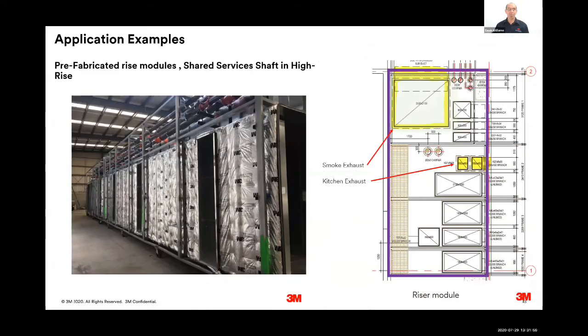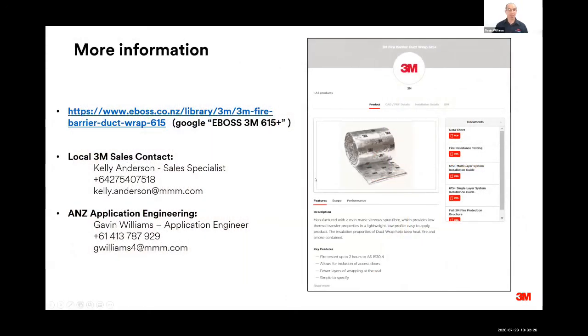And another example where we can use duct wrap for prefabrication, where you might have a central shaft in a high-rise building where a range of services are being shared. In that case, you can fire separate the ductwork from those other elements using 615 plus duct wrap, and that can be prefabricated to speed up the build. So I hope that you learned a few things about how ducts are treated in relation to fire protection.